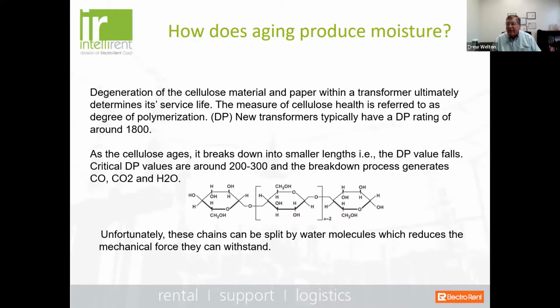In insulation itself, we refer to the term degree of polymerization, and that is the actual strength of the resin bonds in the insulation itself. A brand new transformer will typically have a DP rating of around 1800. Now, as the cellulose starts to age and degenerate, at the end of its life cycle we're probably talking about a degree of polymerization of about 200 to 300. And the breakdown in this process contributes to moisture. And the older it gets, it kind of compounds itself. But when you split these chains by water molecules, that reduces the mechanical force the insulation can withstand. So that's important to know.